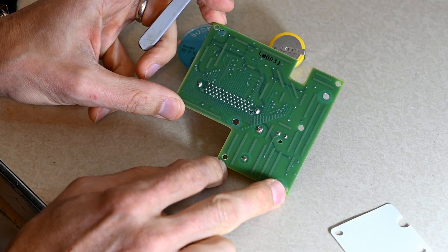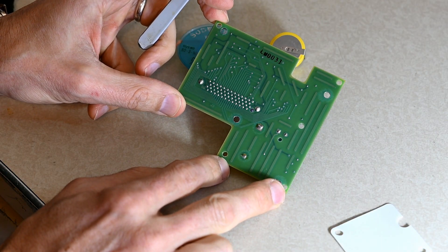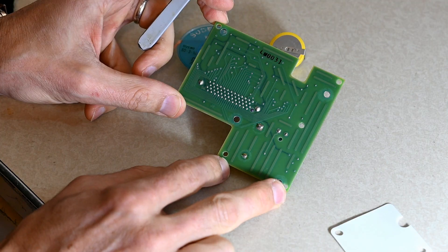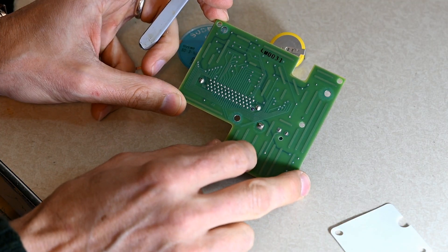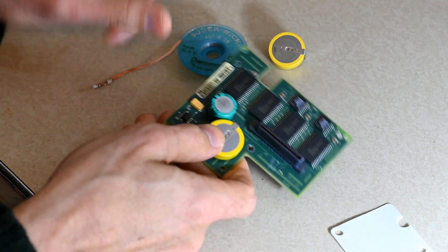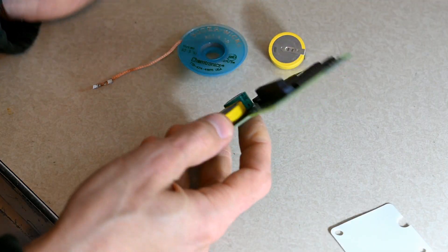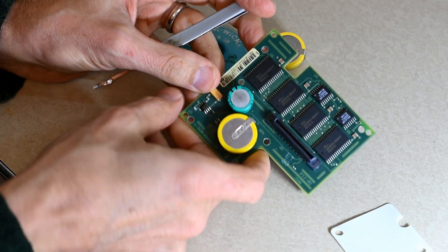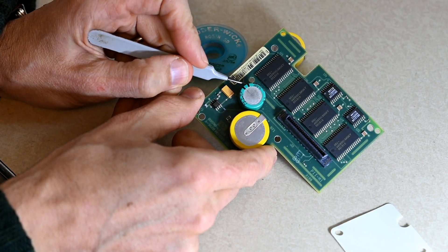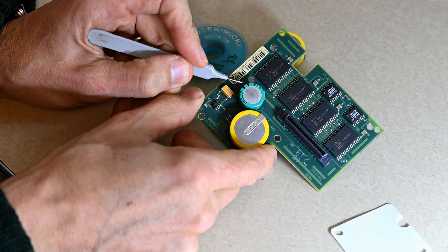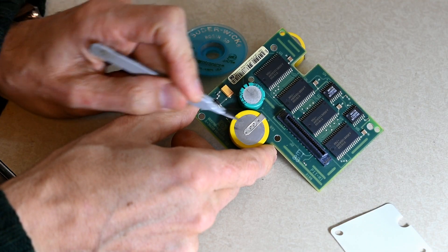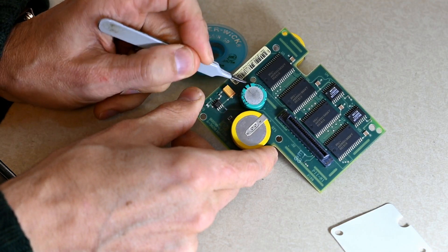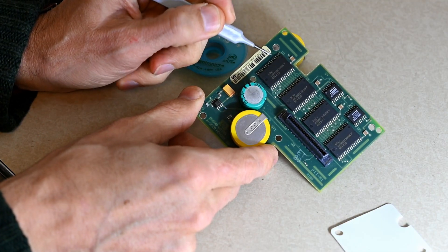So it's been about 20 years. These should be replaced every eight years according to Hewlett-Packard, otherwise you risk losing the data and some of your calibration constants, which would not be good. So let's hope that this works. There is a backup capacitor here which is supposed to hold the charge for about eight hours so that you can swap this battery without losing any calibration constants.